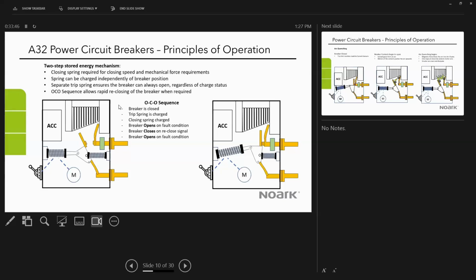And there's a separate trip spring. So the way this works is the spring that you see on the left-hand side is charged either manually with the handle or through the motor operator. And that's the closing spring. And when it closes the breaker, it compresses the trip spring. And so what that means is that the trip spring always is compressed when the breaker is closed. And that means the breaker can be opened regardless of what happens with the charging status of the closing spring.